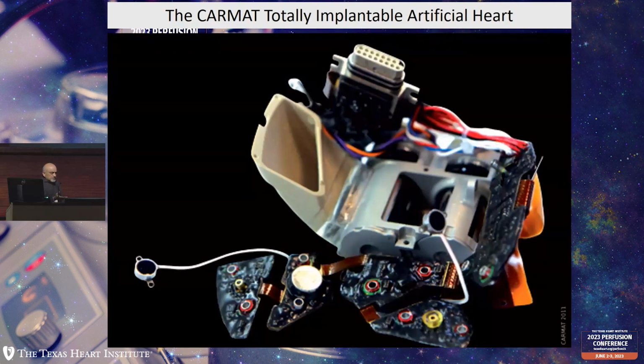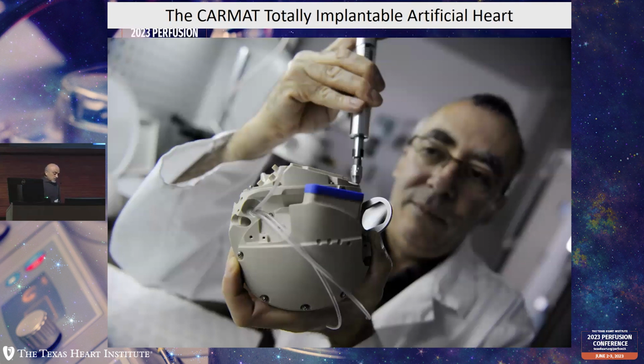As you can see, it's pulsatile, and it's pneumatic pulsatile. I think it has a silicone oil in it that moves the chambers and moves the volume accordingly. Now, it obviously has valves and has lots of moving parts, so we'll have to see the short and long-term durability. Also, it's a fixed size, right? So you can do only so much with a fixed size, especially with the pulsatile. If you have a fixed stroke volume, 50 cc, 80 cc, whatever the heart you made, it's a fixed cardiac output. If you want to improve or change the cardiac output, you have to change the beats per minute, and you're going to have a limit on that.